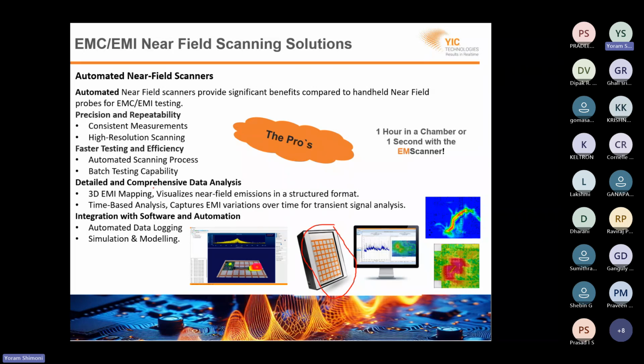And of course, the resolution is much, much higher than the resolution that you can achieve by hand. Faster testing and efficiency, this is the overall of the process, because the time it takes you to scan the DUT depends on the resolution that you've selected. So native resolution is 7.5 millimeters. That means that every 7.5 millimeters, we are making a real-time measurement. But the highest resolution is sub-millimeter, actually very, very tiny, 0.06 millimeters. So obviously, if you want to scan at that resolution, that will take time.